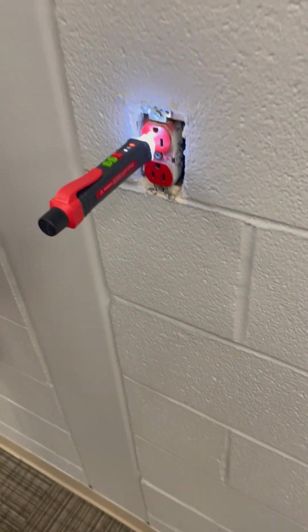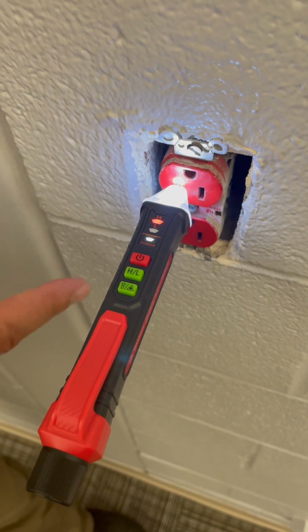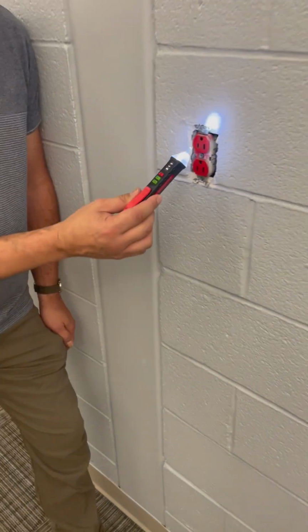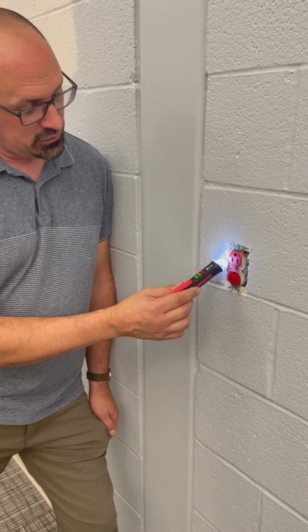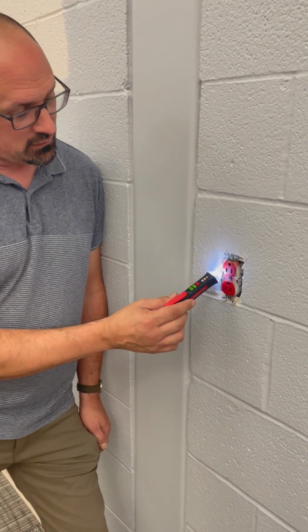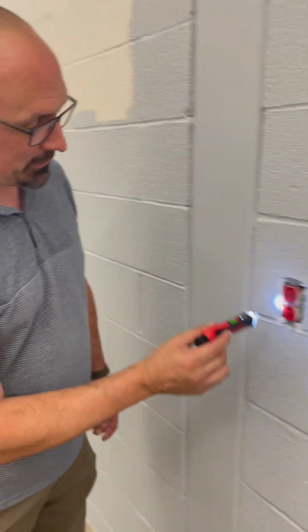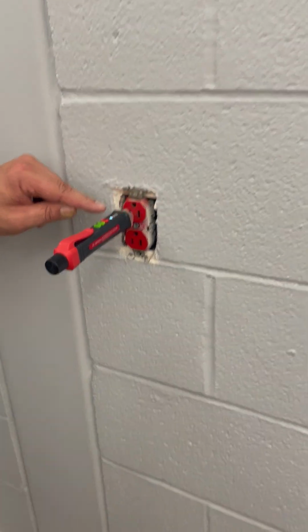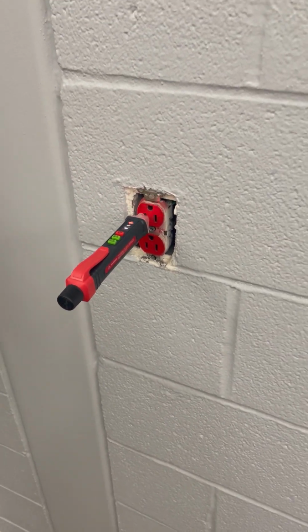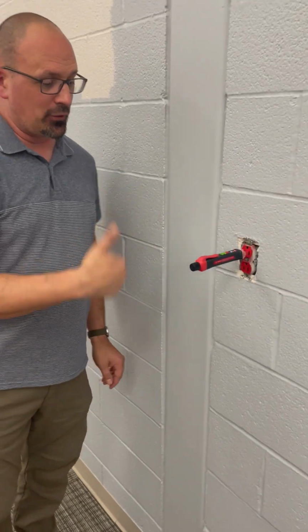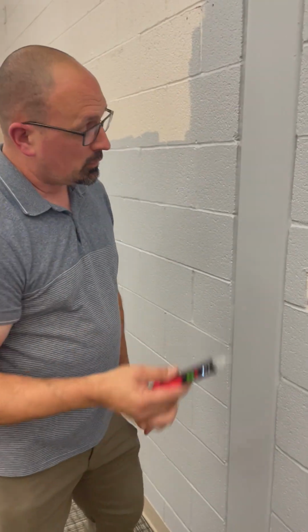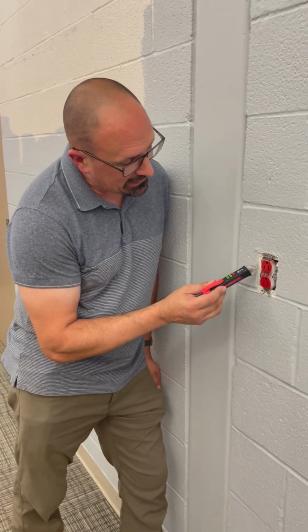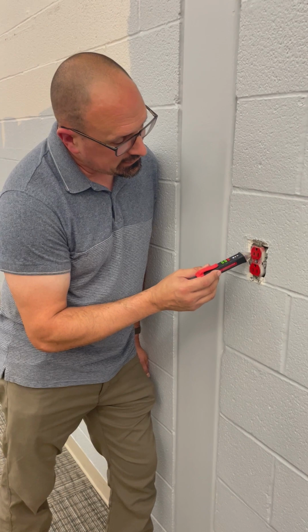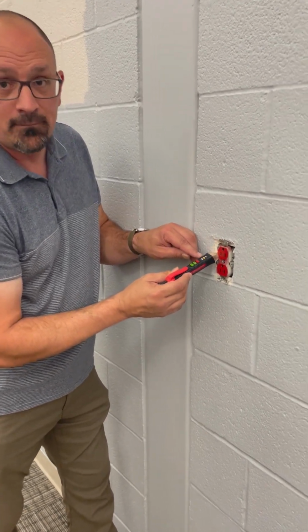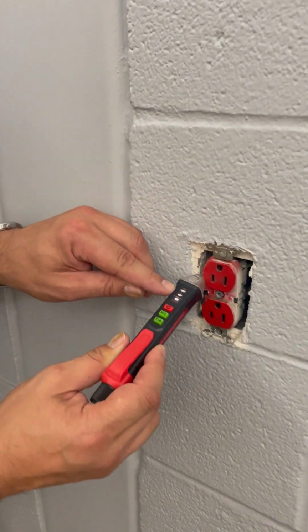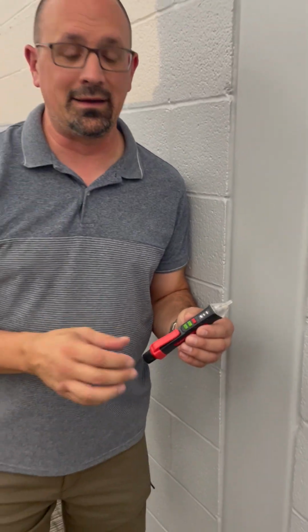This is called a no contact tester, but obviously you can see contacts being made. If you get close enough, you don't have to connect to it to read voltage. But this is the interesting part. When you put this in here, it's reading high voltage, and anything after 12 volts with this is high voltage. 12 volts and below is low voltage. But when I do the no contact test and come out near where that hot is hooked in, it's reading low voltage. Why? Because I'm not directly connected to it, so it's not giving me a true reading.